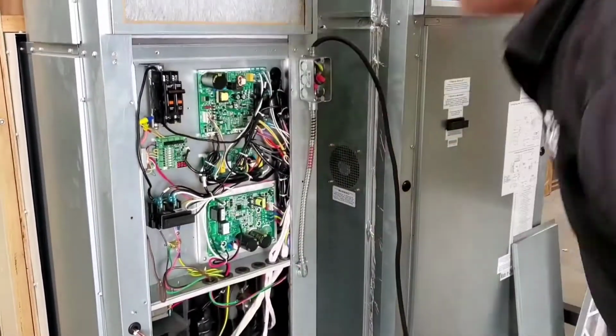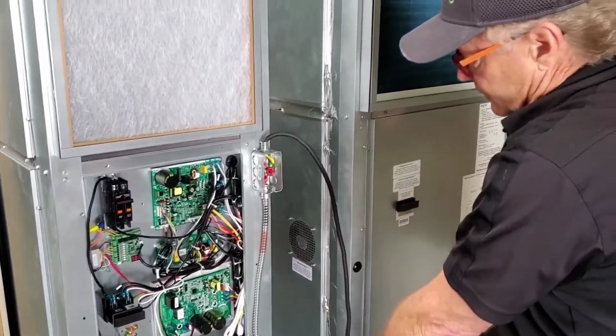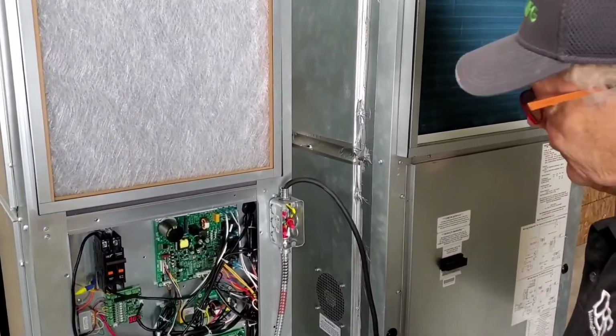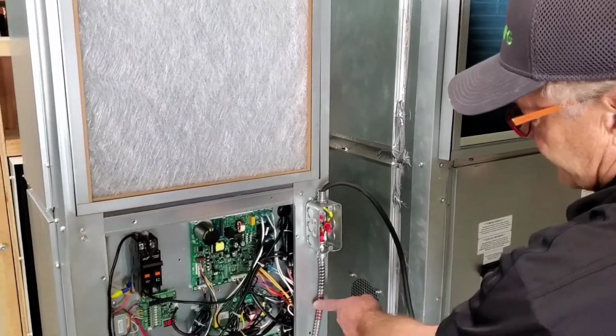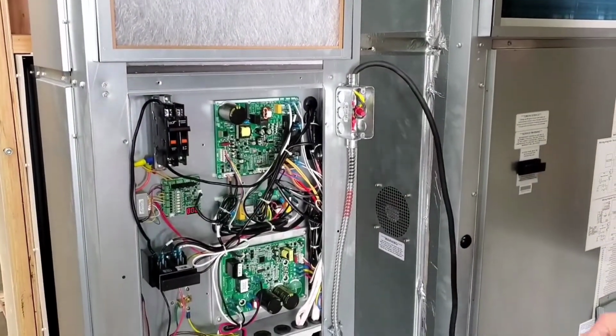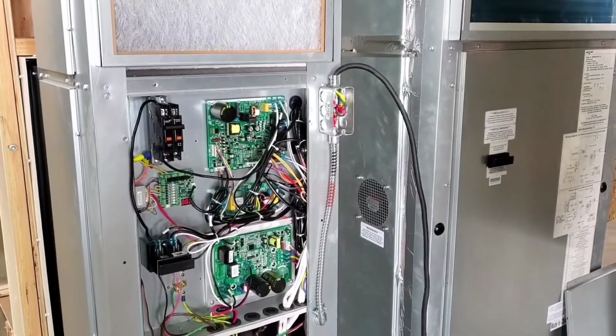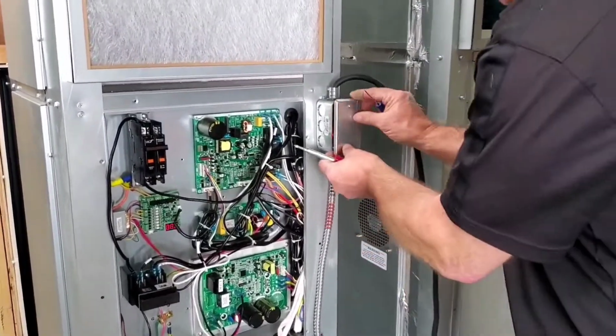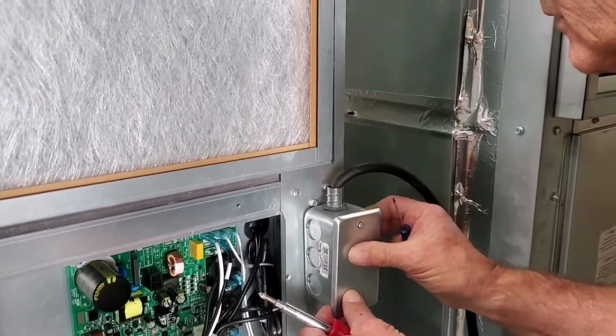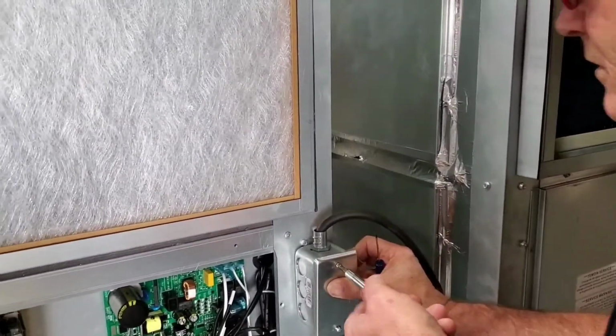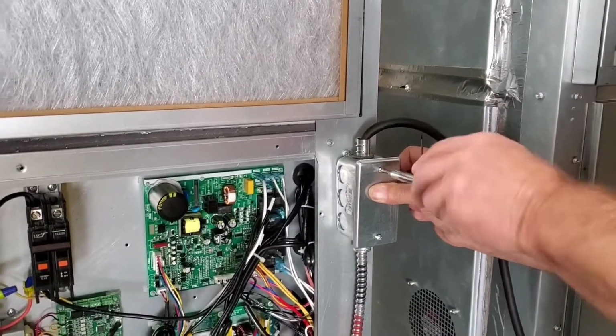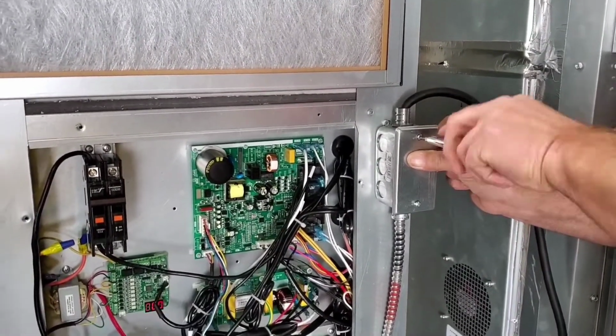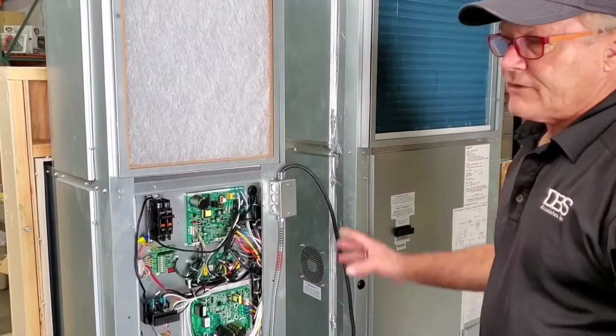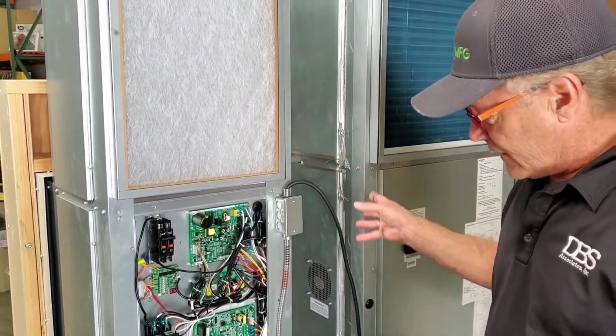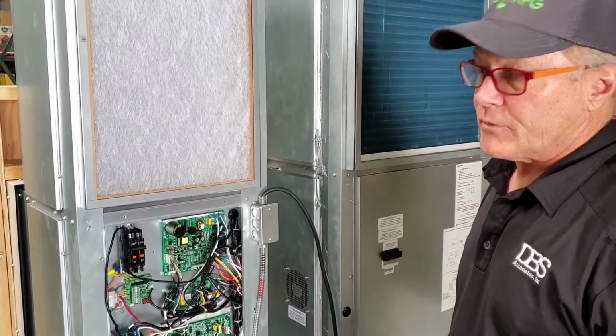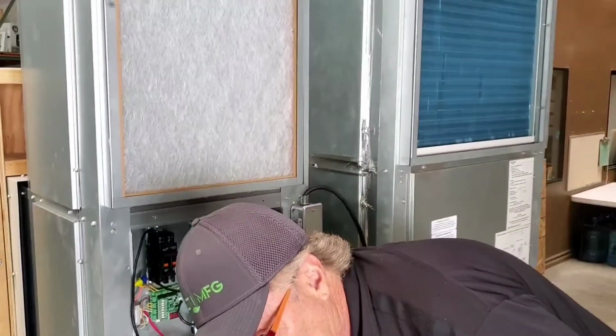While we're waiting for that, on this J-box configuration, you can see what I've used there. You can use half-inch steel flex, whatever you're comfortable with. But I recommend steel flex because it seems like the quickest way to get it all done. Make sure you put a cover plate on your J-box. Now, being that this unit is so much quieter than the competition that you're changing out, you'll have less room complaints from occupants, but you'll also have less awareness of the compressor running.